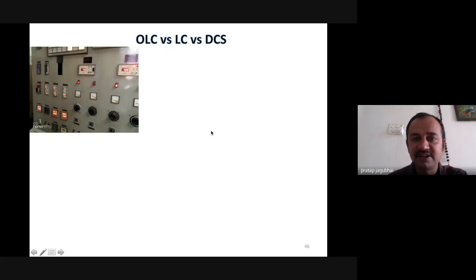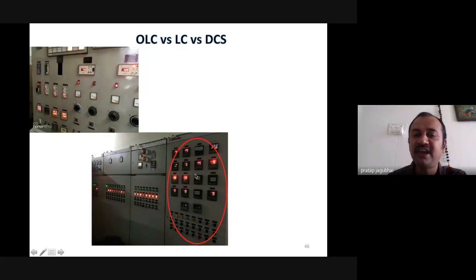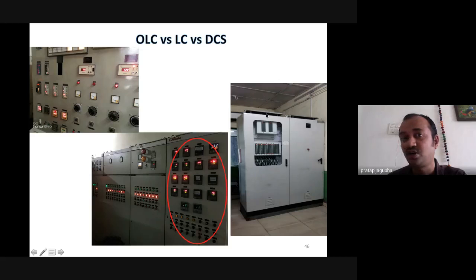I will give you the example of a typical boiler. In open loop control, manual human intervention is always required to control the parameter, to control the pressure. He adjusts the feeding, he adjusts the temperature for the temperature control, he adjusts the parameter. So this is manual control, and it will not suffice for the dynamic response. On top of that, we can have PLC based local control, or a controller inbuilt for the respective parameter, which gives some good control above open loop control. But a distributed control, which is centralized, has better justification in terms of dynamic response, better performance and better efficiency.